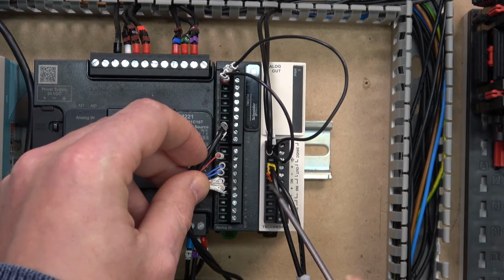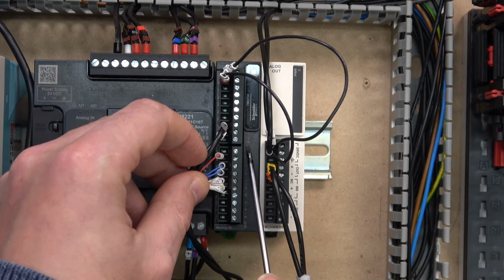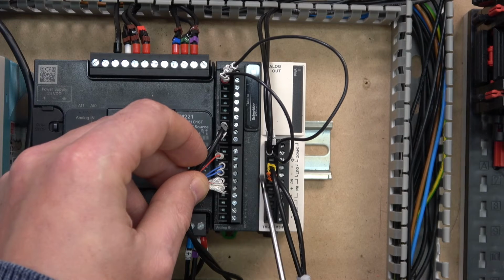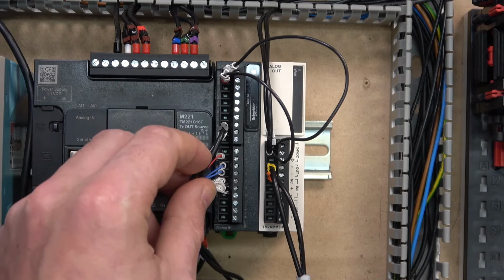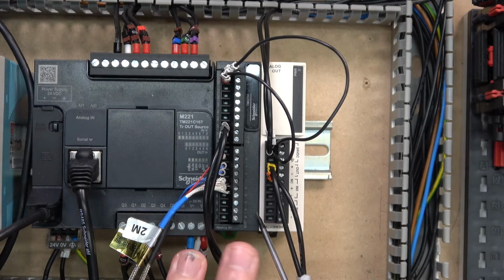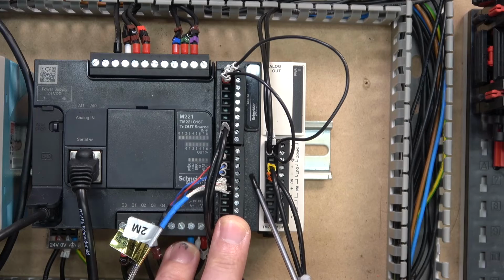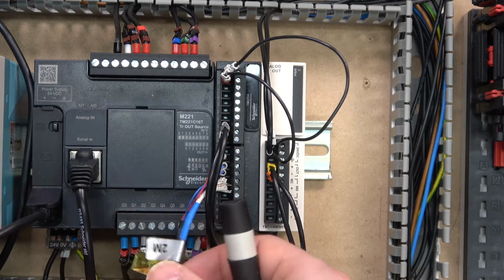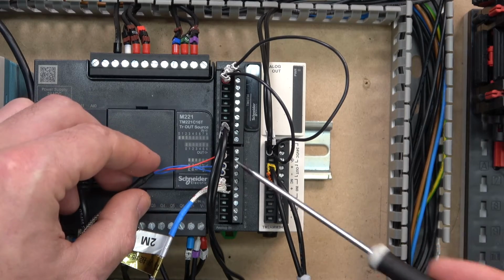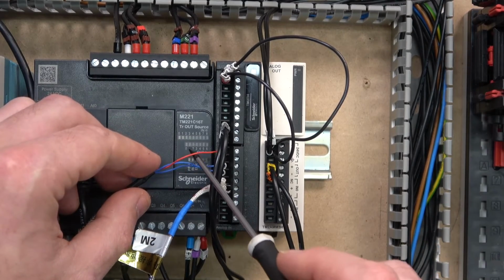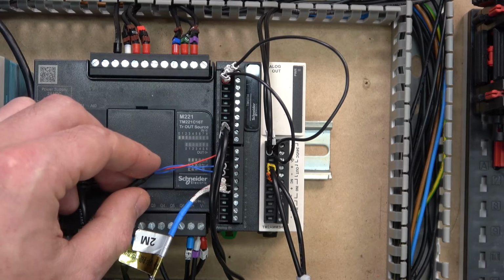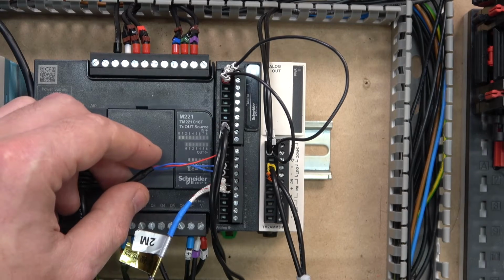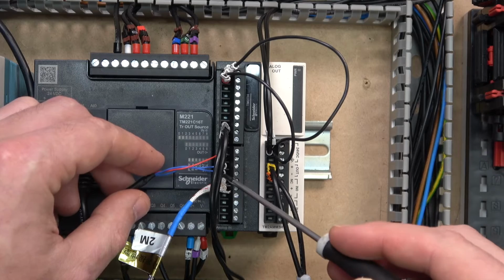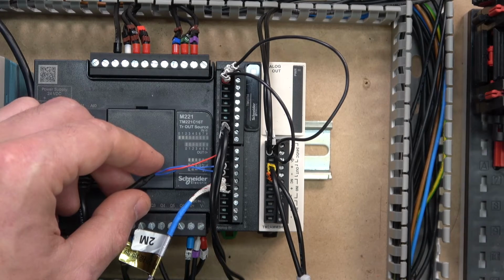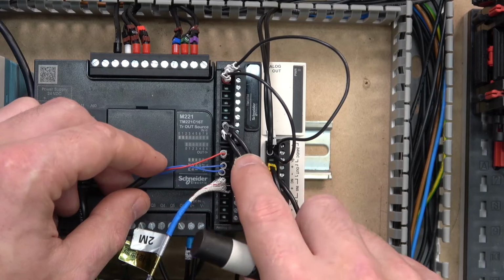As you can see in here, right on the side, it's got B, B, A, B, B, A. That's for the RTD, to indicate to you how you need to wire your PT100. With PT100 temperature probes, in most cases you will have some form of coloring coming with it. As you can see, I've got one red and two blues. If you're not familiar with how they are wired inside the probe itself, these blues more or less meet up in the middle. In some cases you don't even need the third wire, but in our case we are going to use it.